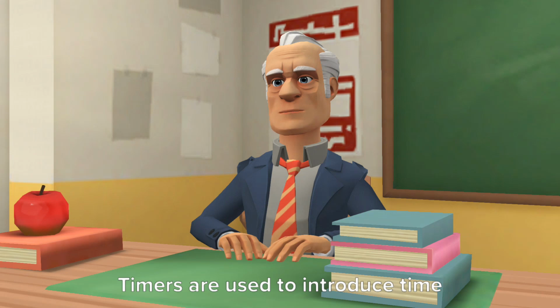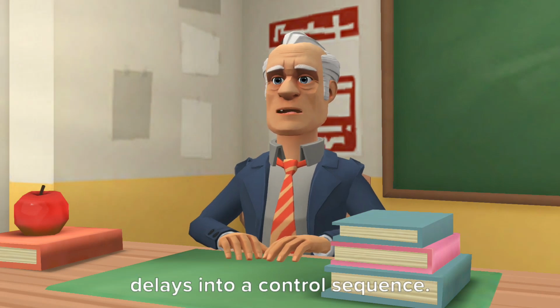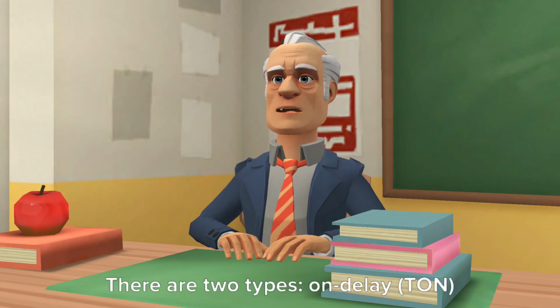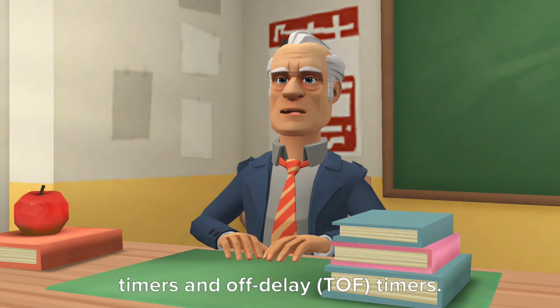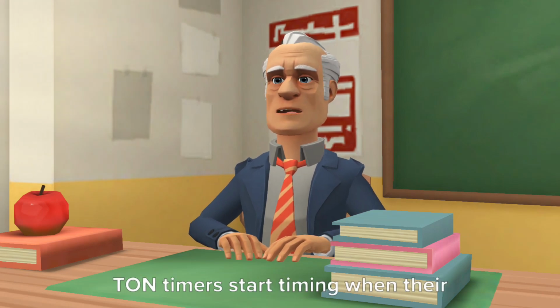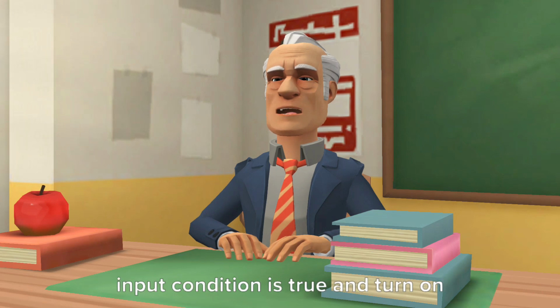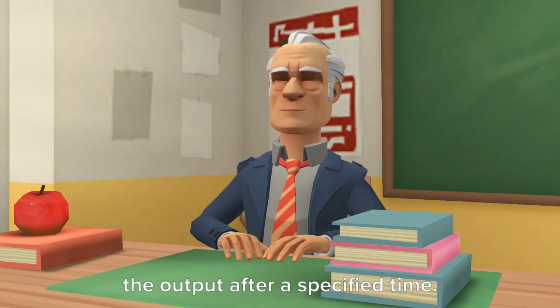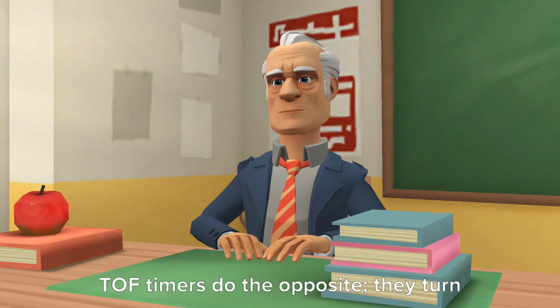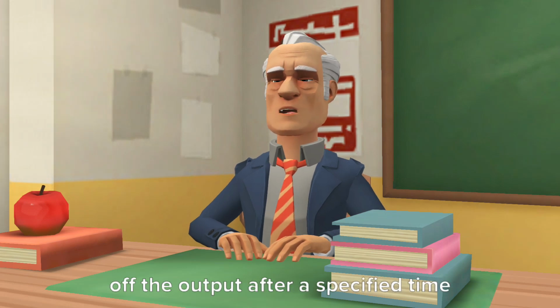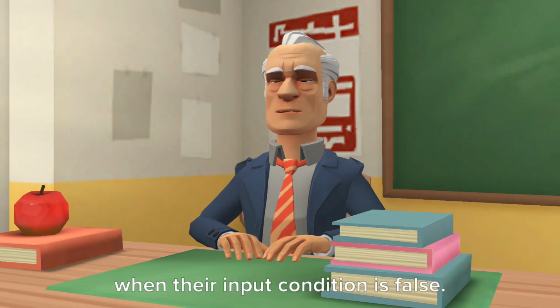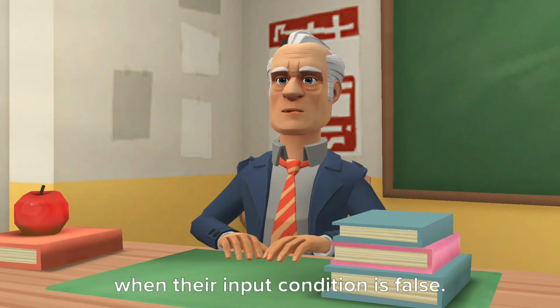Timers. Timers are used to introduce time delays into a control sequence. There are two types, on-delay, TON, timers and off-delay, TOF, timers. TON timers start timing when their input condition is true and turn on the output after a specified time. TOF timers do the opposite. They turn off the output after a specified time when their input condition is false.